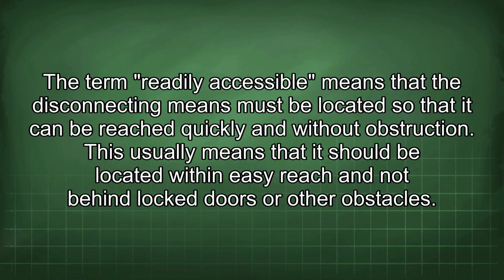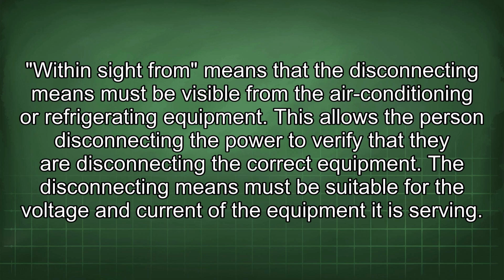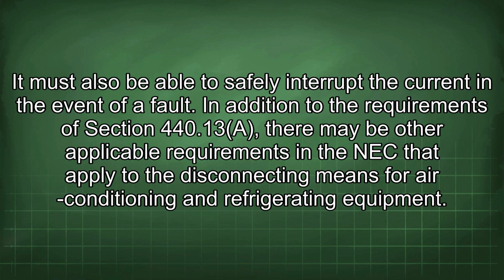disconnected. The term readily accessible means that the disconnecting means must be located so that it can be reached quickly and without obstruction. This usually means that it should be located within easy reach and not behind locked doors or other obstacles. Within sight means that the disconnecting means must be visible from the air conditioning or refrigerating equipment. This allows the person disconnecting the power to verify that they are disconnecting the correct equipment. The disconnecting means must be suitable for the voltage and current of the equipment it is serving. It must also be able to safely interrupt the current in the event of a fault.